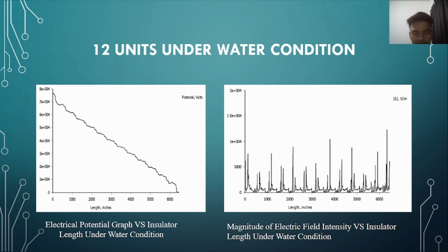We can observe that even though the insulator has the same fringe pattern, the readings are different due to the water on the insulator, because water is a conductor. When it falls on the insulator, an electric field is created at the end of the insulator cap where there is water, causing an increase in electric field strength.